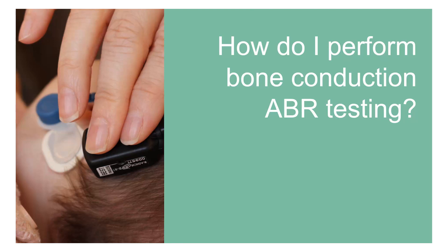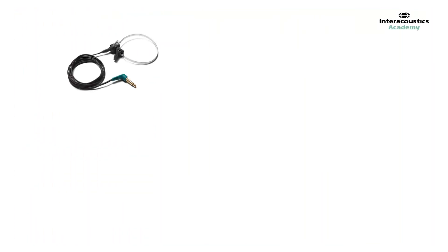Performing bone conduction ABR testing can seem daunting at first, however it is actually very similar to performing air conduction ABR testing. The main difference is obviously using a different transducer. It is essential to ensure your bone conductor is connected to the Eclipse hardware correctly and calibrated annually to the appropriate standards.